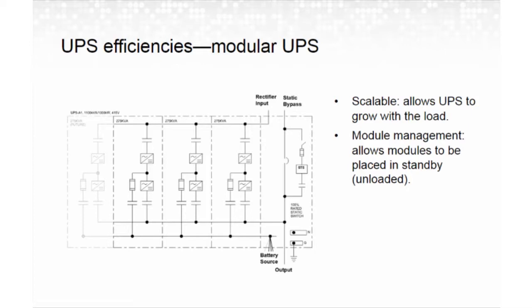Another thing some vendors are doing is what they call module management. Basically it allows you to place modules that aren't being used in standby. So in this instance, if I had a load that was 200 kW, I could put the third module, even the second module, in standby, and the single module now can be operating higher on that efficiency curve.